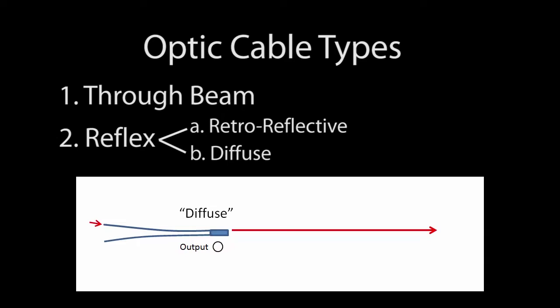Diffuse is the same setup, but now we wait for an object to pass by and reflect light back to the sensor. So since the object is reflecting light back to the sensor to trigger the output, we call that light on.